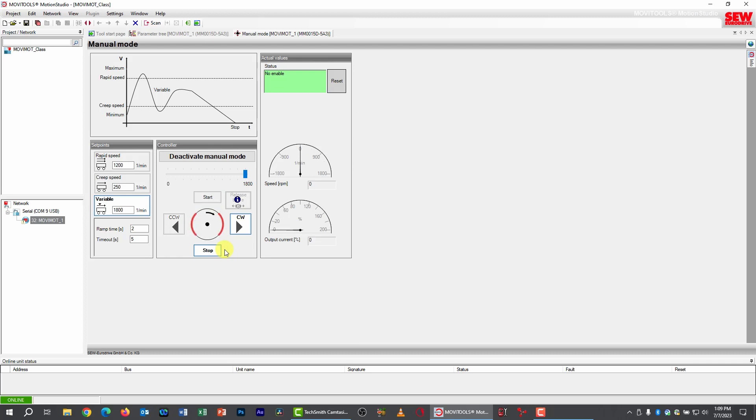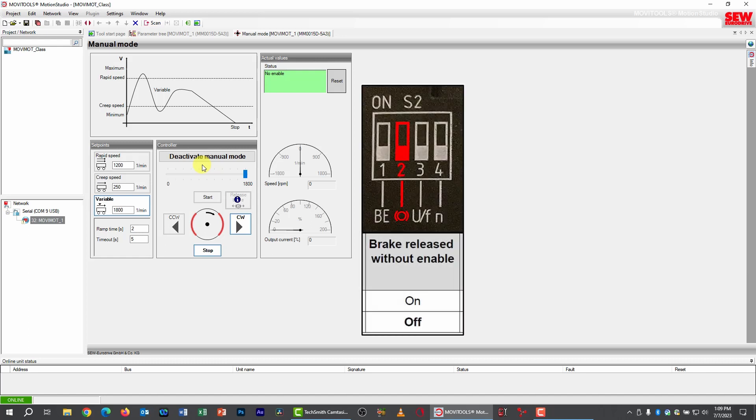All right, let me show you something else in the parameter tree. You may have wondered why do we have this button that says release brake and it's grayed out. Well, I'm going to explore something I've mentioned a few times but never demonstrated, and that is the ability to release the brake without actually enabling the motor. You may remember there's a dip switch that you can use in easy mode to enable this feature, and there's also a parameter in expert mode. We'll play with the parameter, but remember you can do exactly the same thing with the dip switch as well.